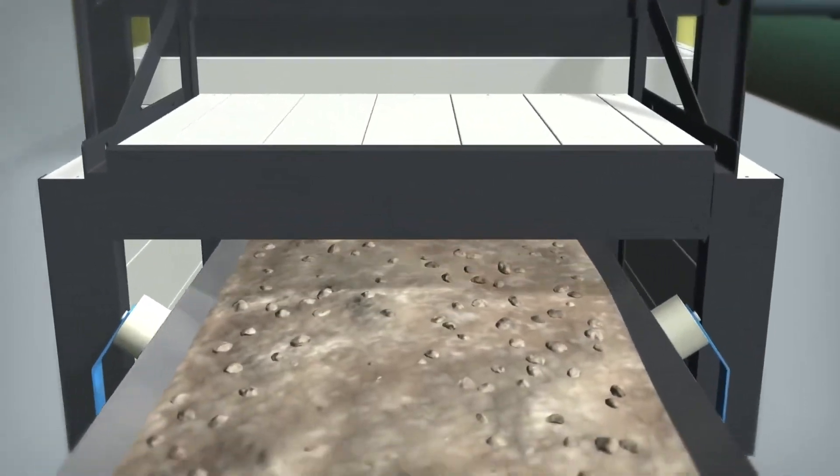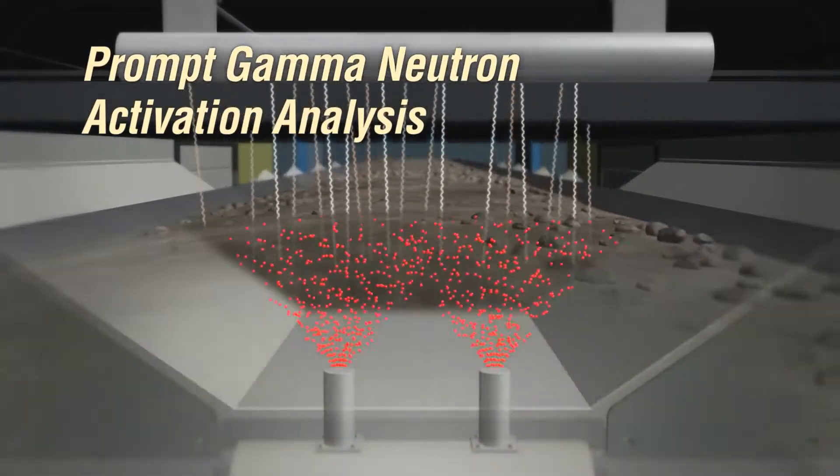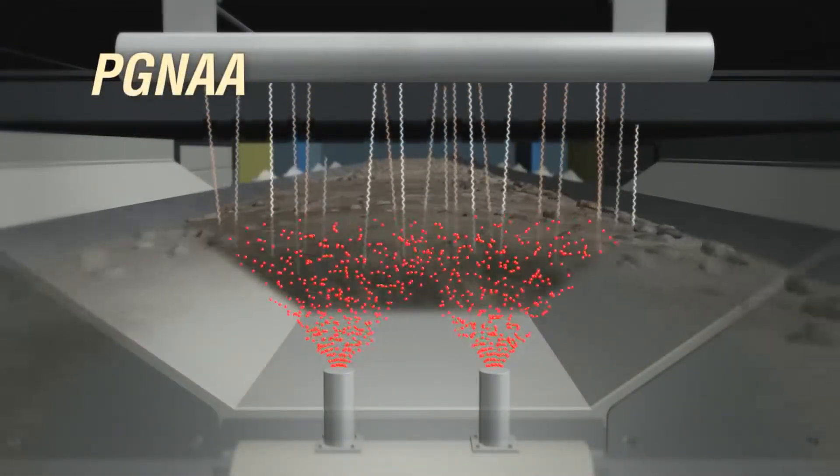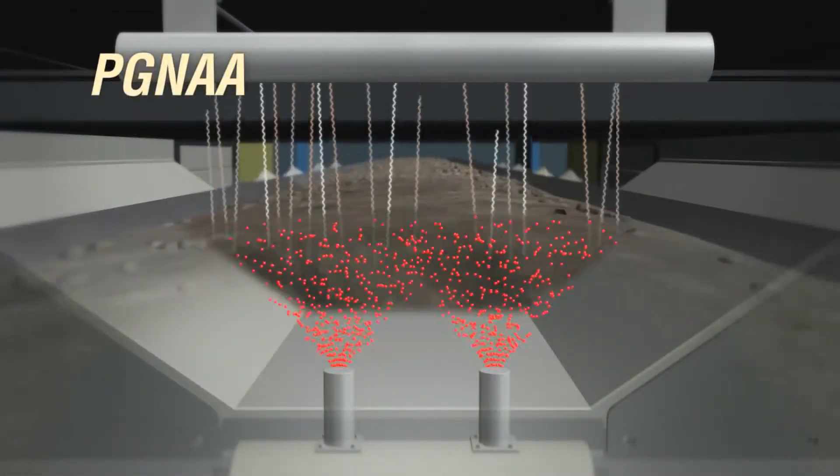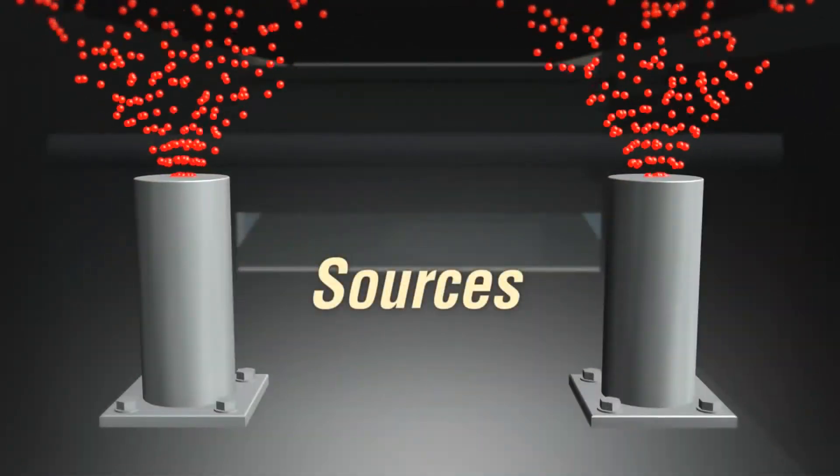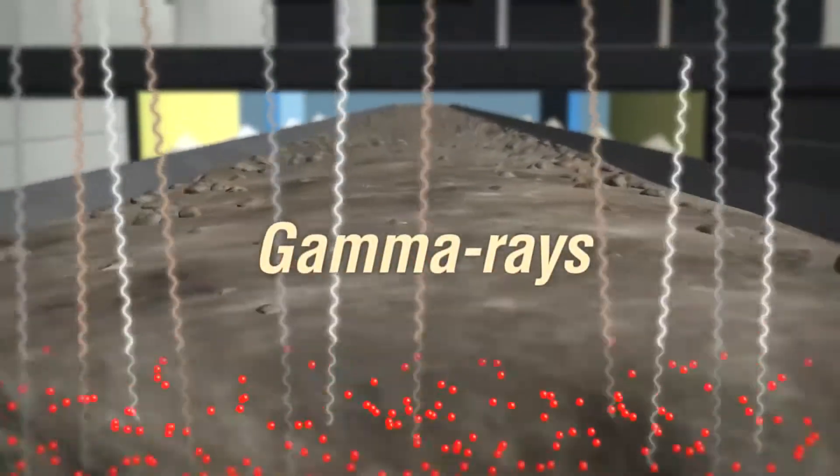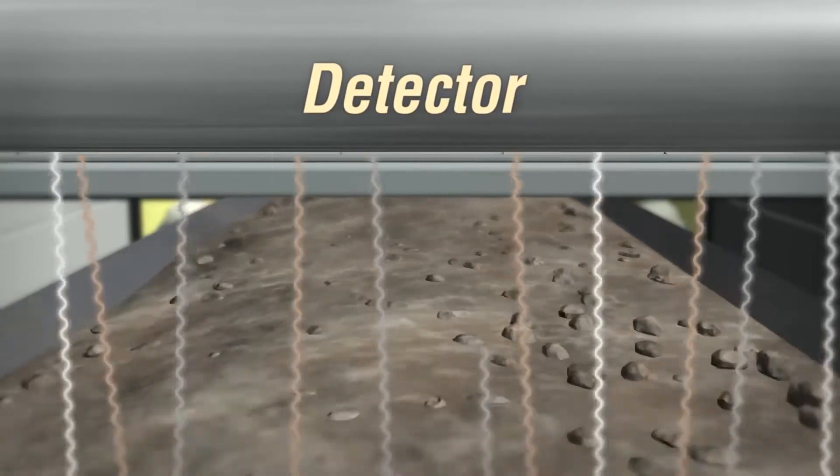Thermo Scientific's CB Omni uses a measurement technique called Prompt Gamma Neutron Activation Analysis, or PGNAA for short. Neutrons from a source located below the conveyor interact with nuclei in the raw materials.